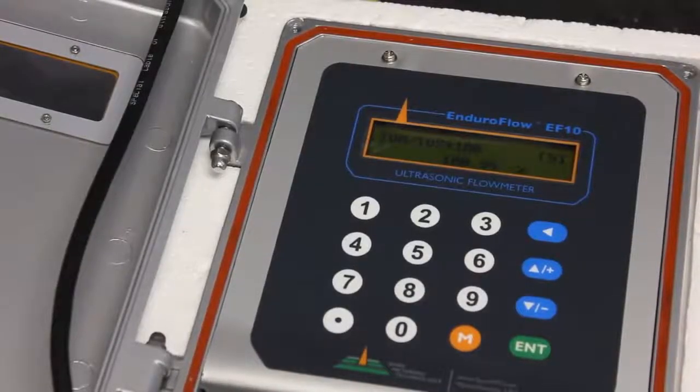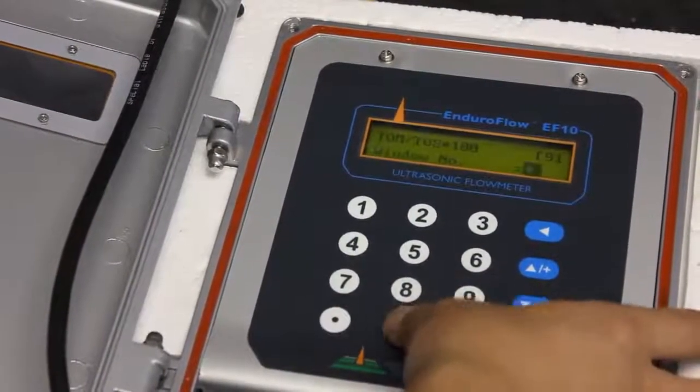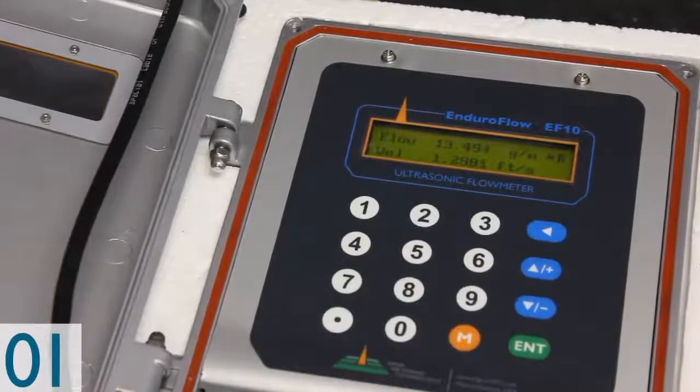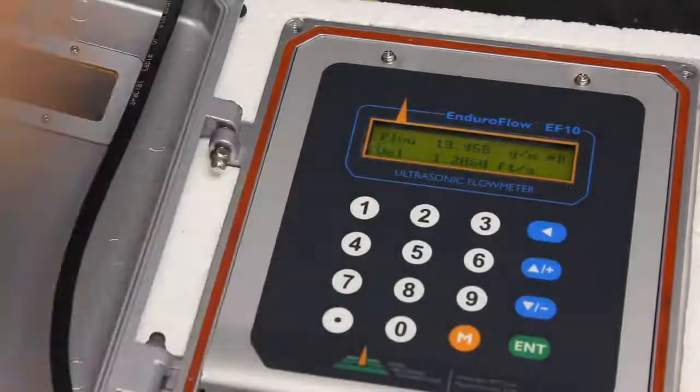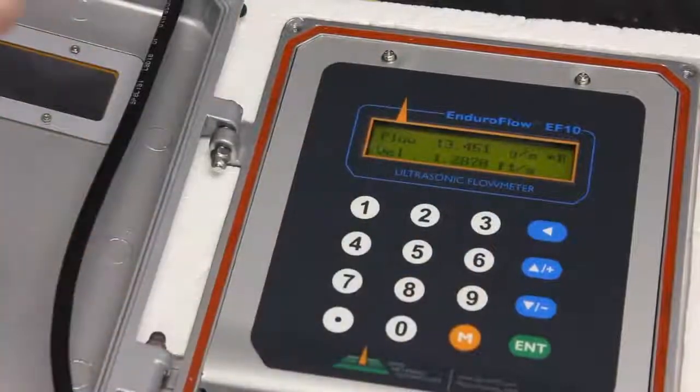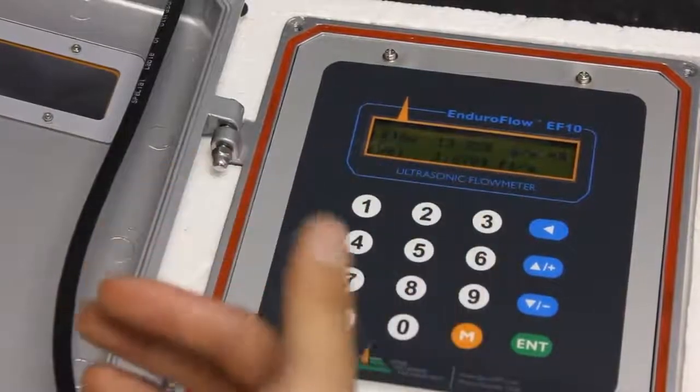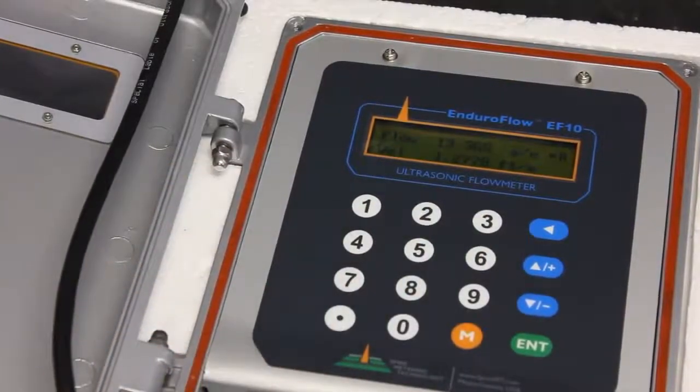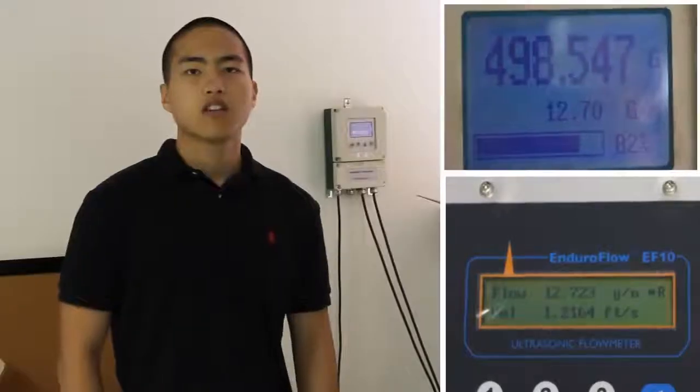Now that we have the value as close to 100 as possible, you can go ahead and check your flow. Menu 01. And make sure that the flow is not negative. The flow should be positive if you have the upstream pointing in the direction of the flow and the downstream pointing against the direction of the flow. If the flow is negative, that just means you need to swap the transducers.